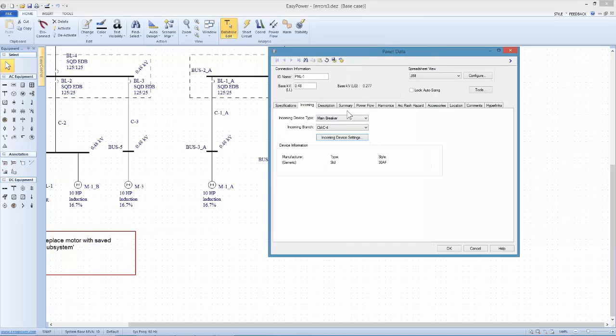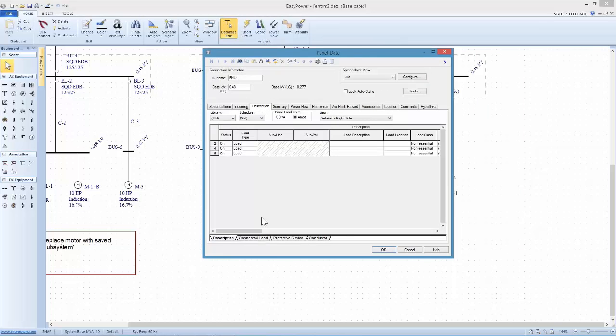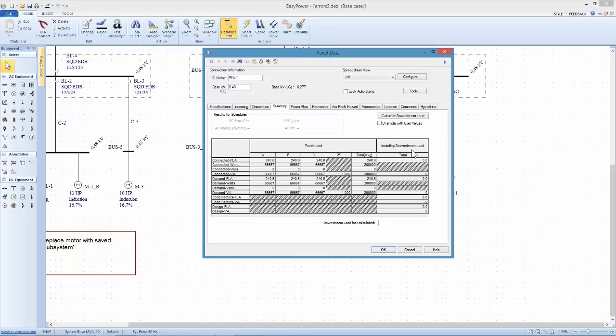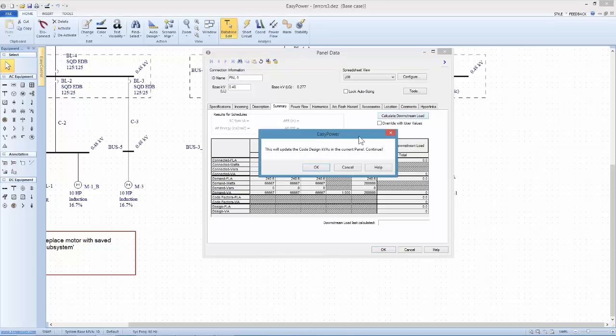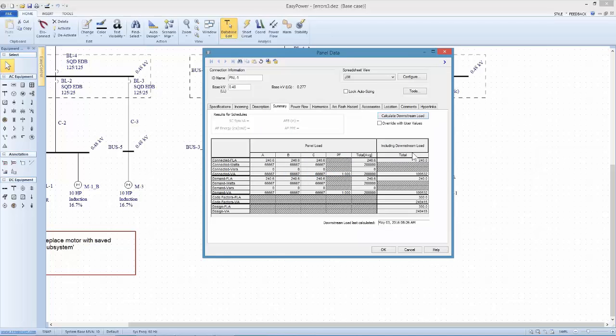Now, even as I complete the entries for all the loads, and in my description of the loads in this panel, I would make entries under the left side and the right side, and I'm going to have some description of my protective devices internally. Once I've completed all those load settings, I want to come to the Summary tab, calculate the downstream load, and it's going to update any sub-panels that are involved. And this is going to give me a total estimate of what the average loading or typical loading is, based upon whatever duty factor I've set or percent loading scale factor I've set for this particular panel.